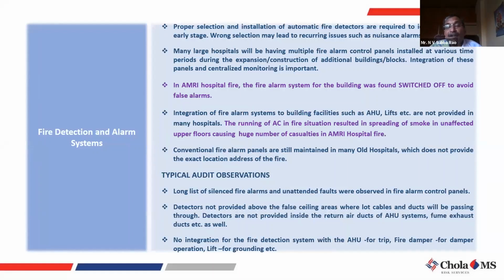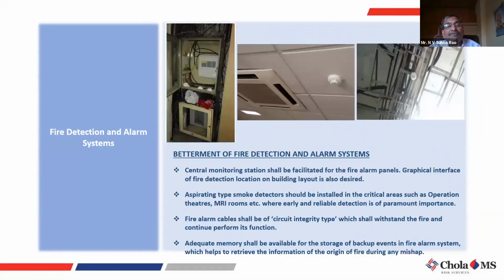The other important point is that in a lot of places the AHUs are not integrated with the detection system. What I'm trying to say is that in case a smoke detector comes into picture, you can have a voting system, but then immediately the HVAC system should stop so that the smoke doesn't spread from one area to the other. Then there are a number of areas that are not covered.